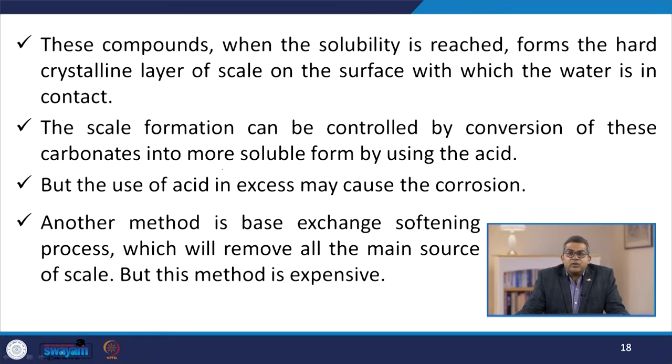When solubility is reached, these compounds form a hard crystalline layer of scale on the surface with which the water is in contact. Scale formation can be controlled by converting these bicarbonates or carbonates into more soluble forms by using acid. However, excess use of acid may cause corrosion. Another method is the base exchange softening process, which removes the main source of scale, but this method is quite expensive.